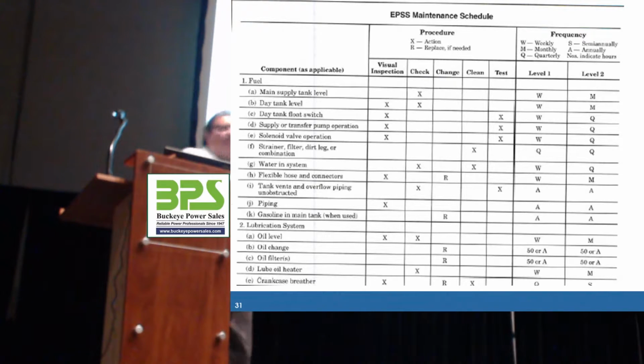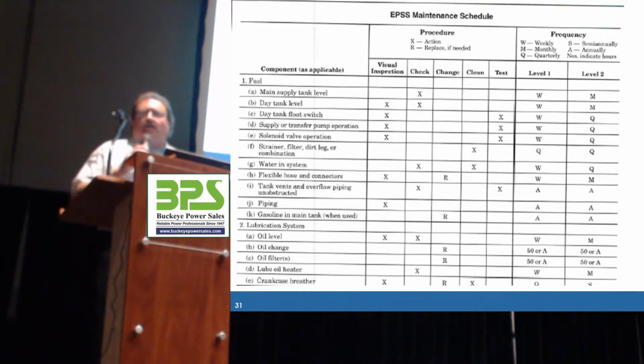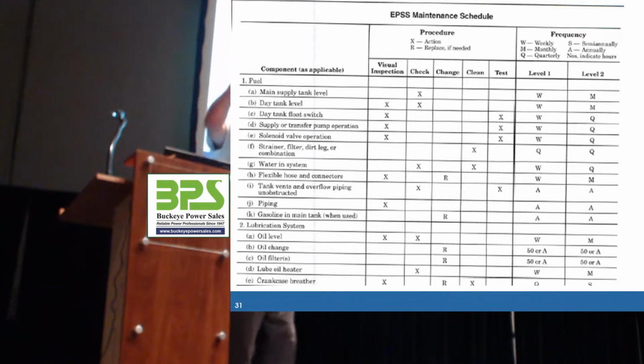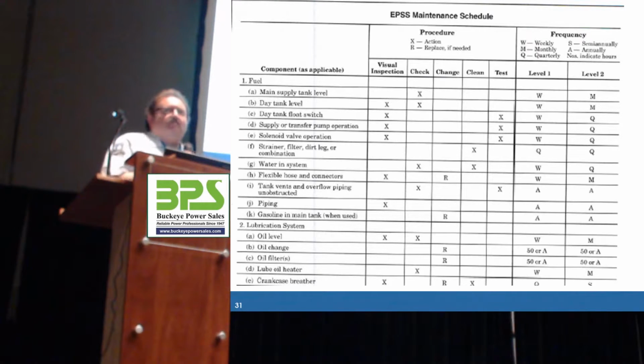Basically, life safety is level 1. It directly affects life safety. If we lose power on this circuit, people can die. Level 2 is life safety, but not quite as critical. It could be your egress lighting. It could be monitoring, but it's not necessarily an operating room that if it goes dead, very bad things could happen. So again, we're wanting to take the highest level that we have and apply it to you so that you can have the best chance of having that 99% reliability. So use the level 1 here. So once a week, you need to check that fuel level, right?